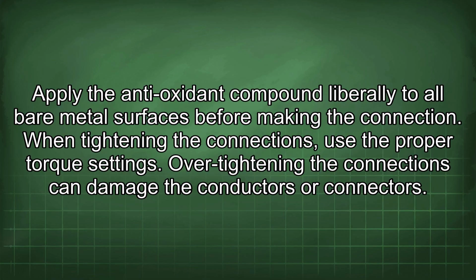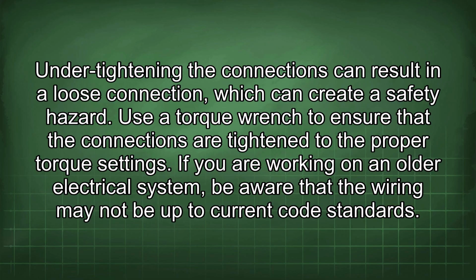Over-tightening the connections can damage the conductors or connectors. Under-tightening the connections can result in a loose connection, which can create a safety hazard. Use a torque wrench to ensure that the connections are tightened to the proper torque settings.